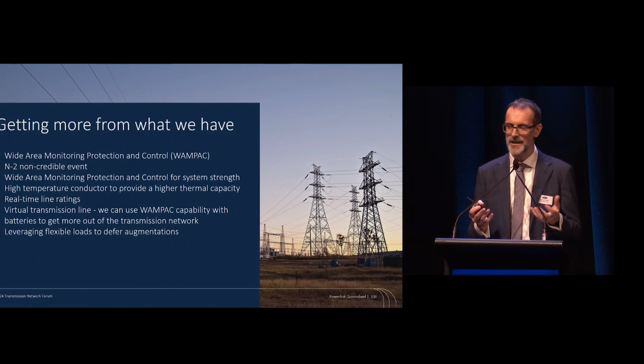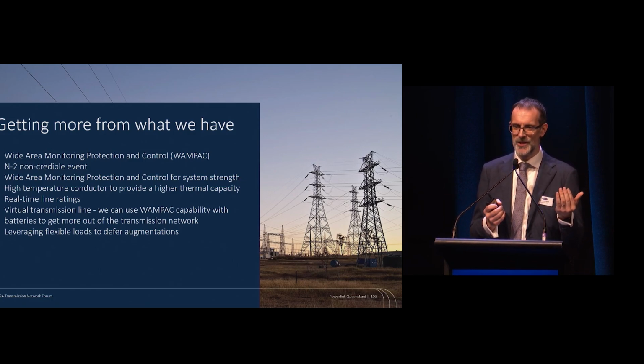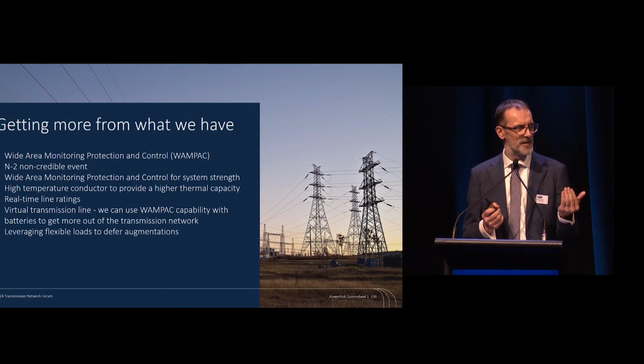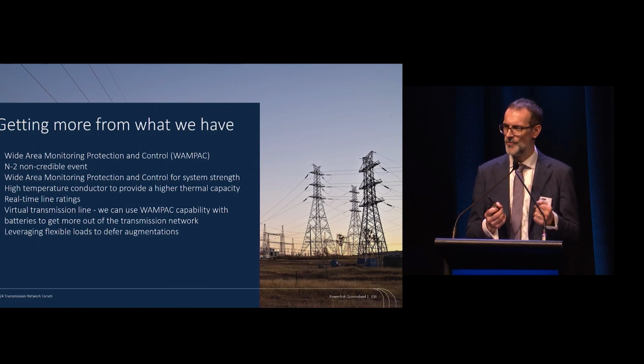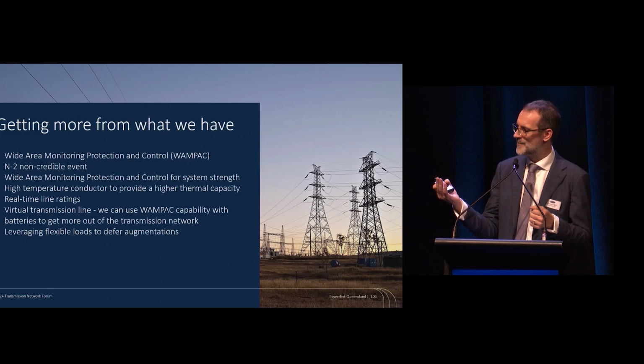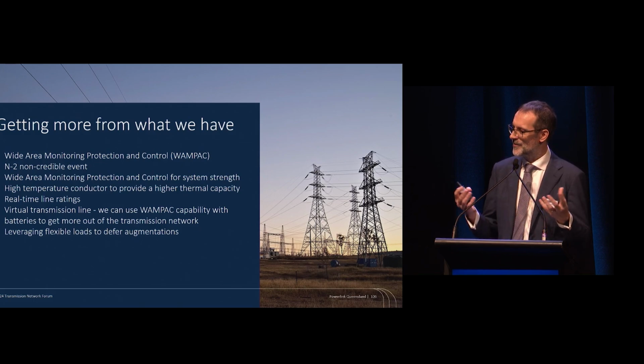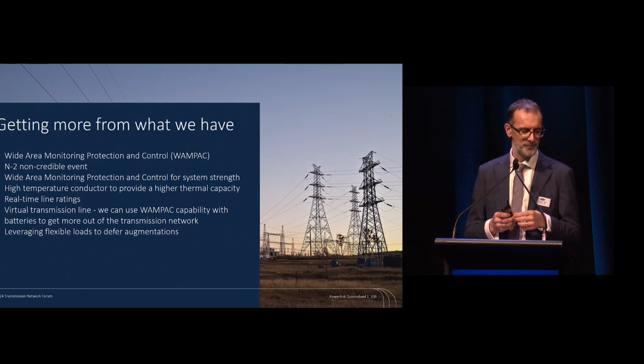Normally, you reduce generation in anticipation of a fault happening. What we're doing with these two is we're actually waiting for the fault to happen and then taking very swift action to keep the network stable, allowing us to get more out of the network.